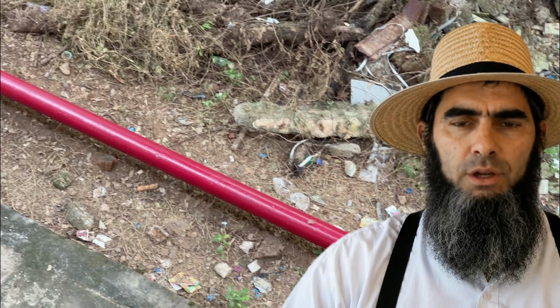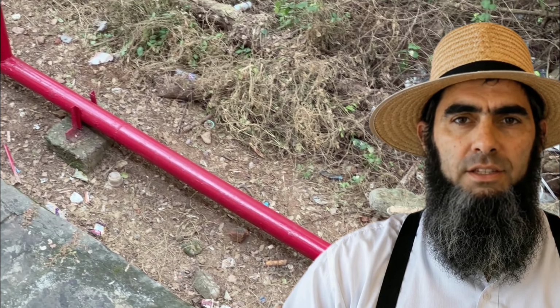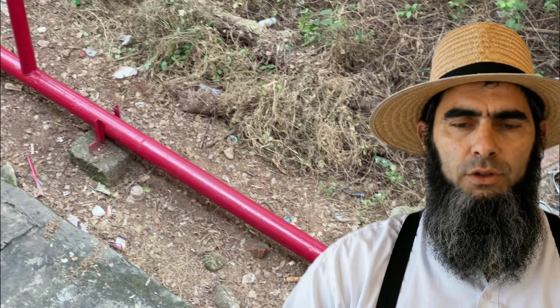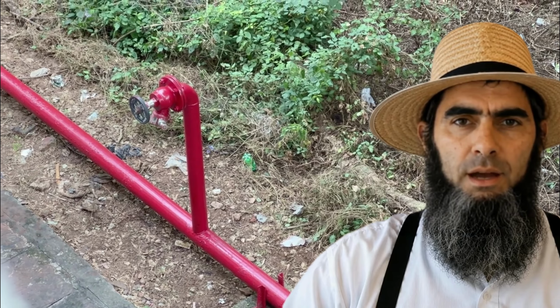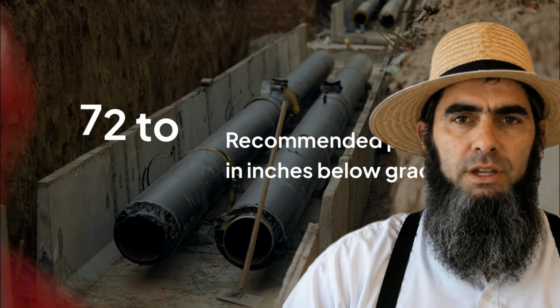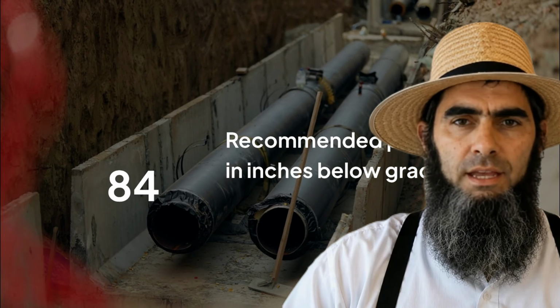I would start with one smooth wall 4-inch Schedule 40 PVC run, or SDR 35 sewer pipe if your soil is stable, at 36 to 60 feet long. Put the top of that pipe 72 to 84 inches below grade if you can. Natural Resources Canada recommends at least 1.5 meters of depth. Performance barely improves after 3.5 meters, so do not chase depth for ego. If you have more room, 2 parallel lines beat one oversized gamble.